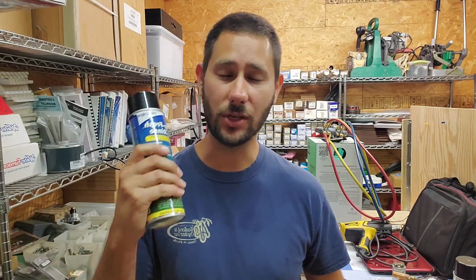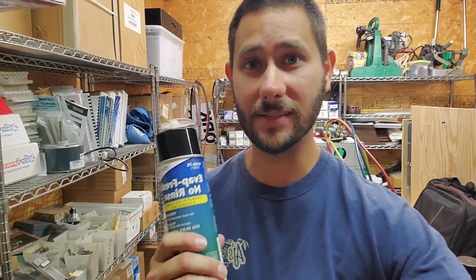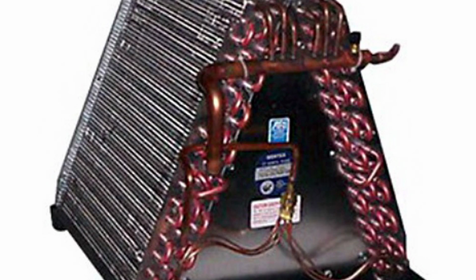You might need some other type of coil cleaner and a water hose and a good nozzle to make sure that you clean it properly so that it won't have any low airflow situation. But a dirty evaporator coil is another reason your unit could be freezing up. So make sure you don't have an evaporator coil that looks like this. Make sure you have an evaporator coil that looks like this. All right, let's go to another reason.